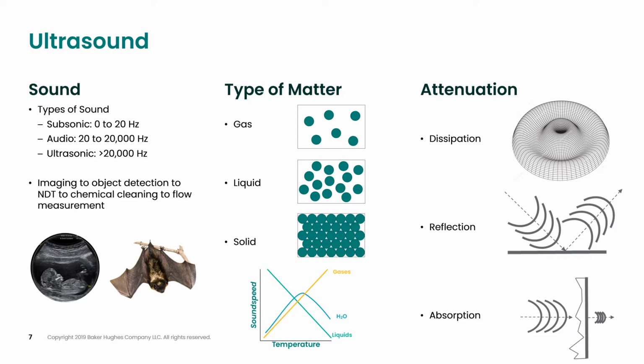Last, absorption occurs when a sound wave is absorbed by the material until it is reduced or lost. Some materials like this might have a rough or even porous surface. In ultrasonic flow, this can be observed with process buildup, corrosion, or even some attenuative gases such as carbon dioxide. Each ultrasonic flow meter is designed to overcome attenuation by the installation method, transducer selection, signal processing, and design experience by a Panametrics application engineer.